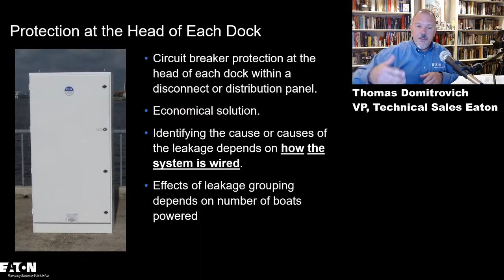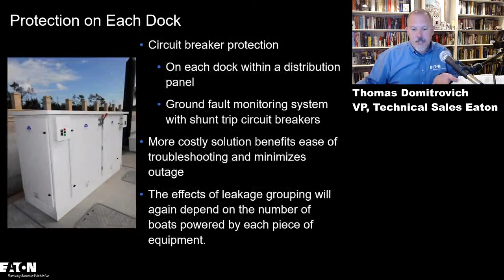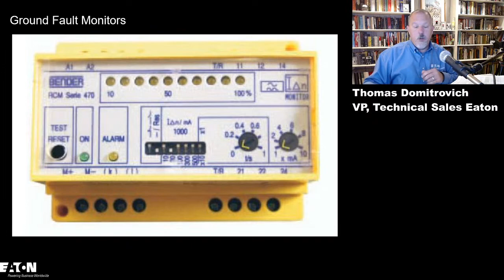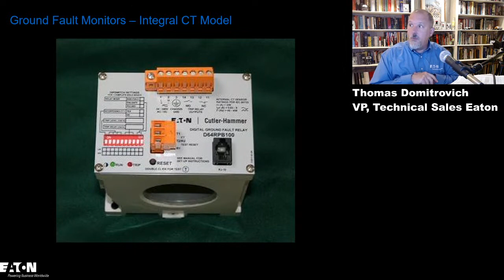But a lot of this is just talking about protection at the head of each dock and how to lay out the system. There are various ways that you can do that. I put a picture here of a Bender relay. You can field adjust these. You can set these to open a shunt trip device. Eaton has the digital ground fault relay as well, which can be used in these applications, with an integral CT. There are different ways you can wire the system. You can either loop feed these, where again in this case you're feeding one, which feeds another, which feeds another.